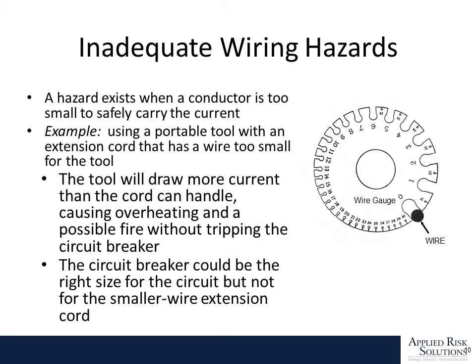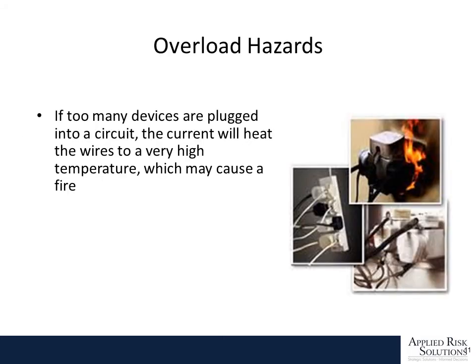But if you're using a portable tool and you have an extension cord that has a small wire on it, or the wires are smaller than the circuit's designed for, the tool can draw more current than the cord can handle, causing overheating and possibly a fire without tripping the circuit breaker. The circuit breaker could be the right size, but because you've introduced a wire into that circuit that is undersized for the circuit, the breaker cannot do its job. Overloading circuits is a serious problem. Don't plug in too many devices into one outlet.